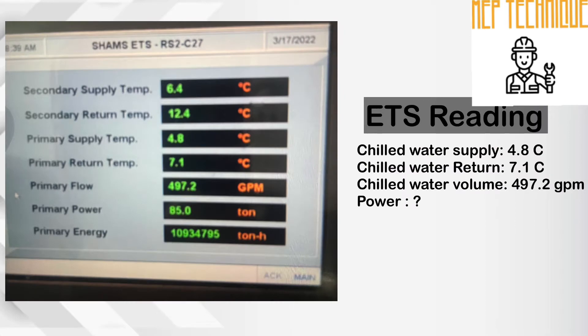The chilled water supply temperature is 4.8 degree Celsius. Chilled water return temperature is 7.1 degree Celsius. And water volume is 497 GPM — GPM means gallon per minute.